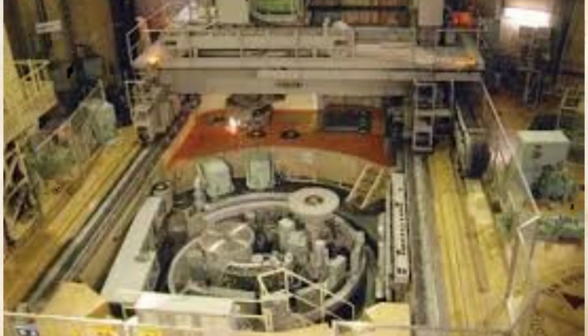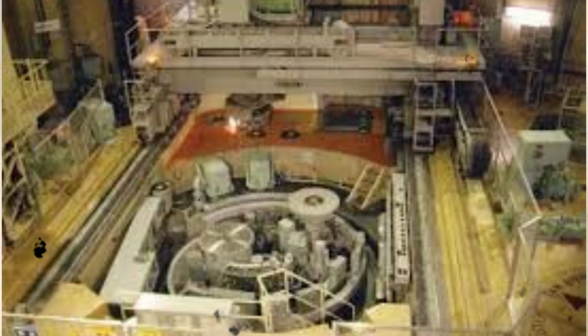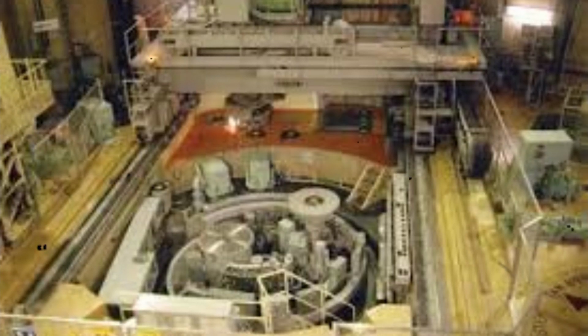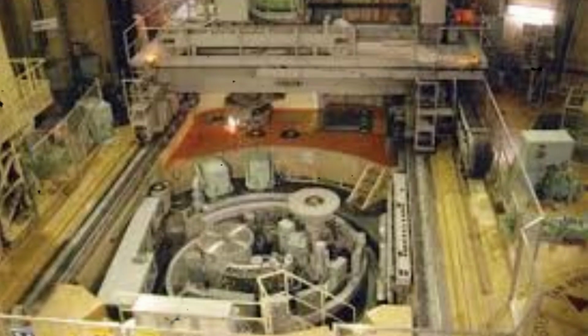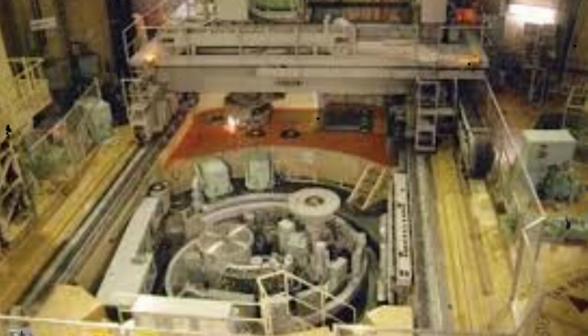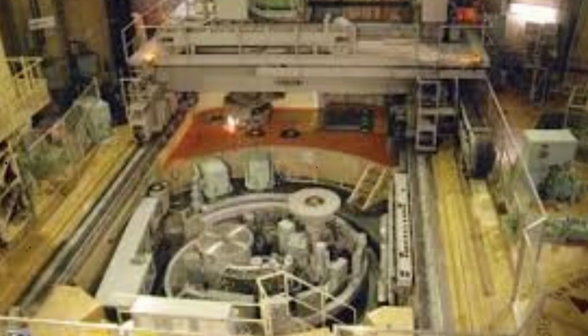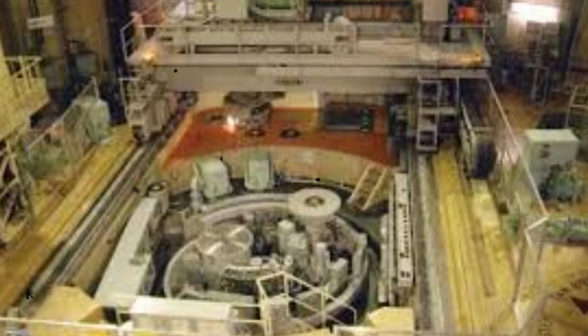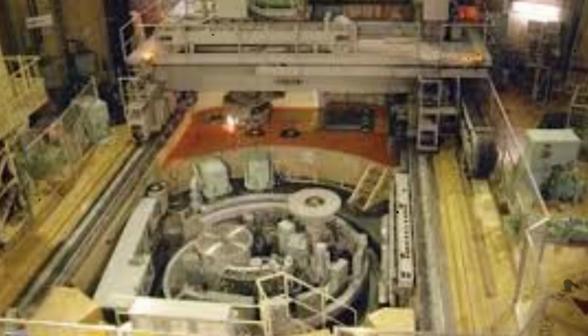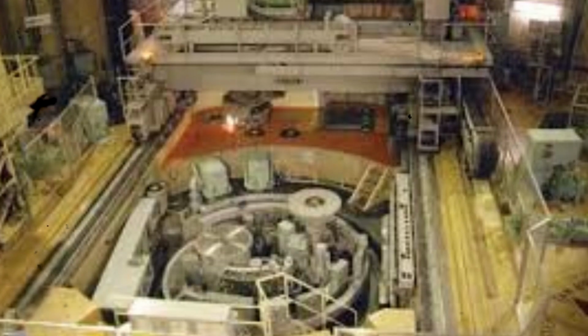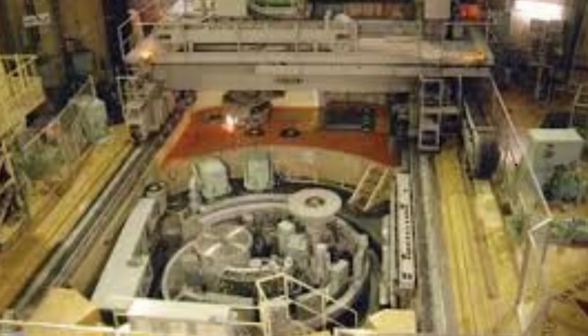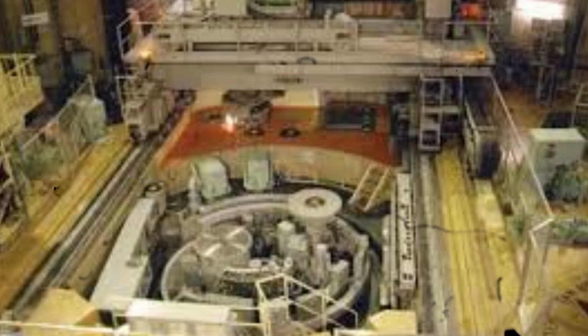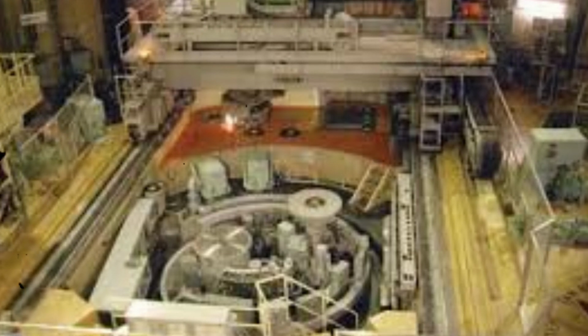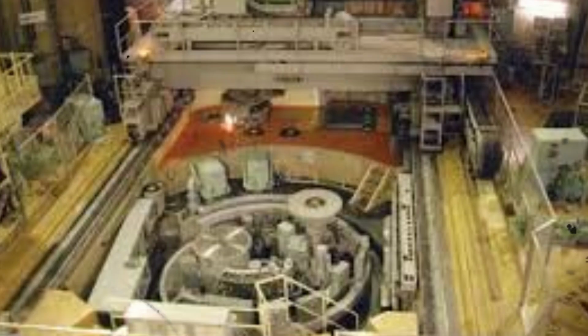When the thermocouple well tip separated from the remaining structure, it created a direct pathway for sodium to escape from the pressurized secondary loop into the piping room atmosphere. The leak rate was determined by the pressure differential across the opening and the effective flow area of the fracture. Initial leak rate was modest because the fracture opening was relatively small, but sodium continued to flow as long as the loop remained pressurized.